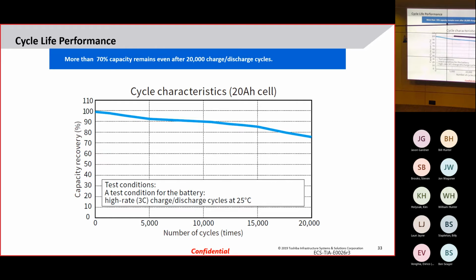We can see in this chart, the 17,000 cycles is 80%. Now, in the United States, a data center would not see that. We're going to see 2 of them a year, maybe, and if you do testing once a quarter, that's 6, so let's round up to 10. 10 per year times 10 years is 100, times 2 is 20 years, that's 200.